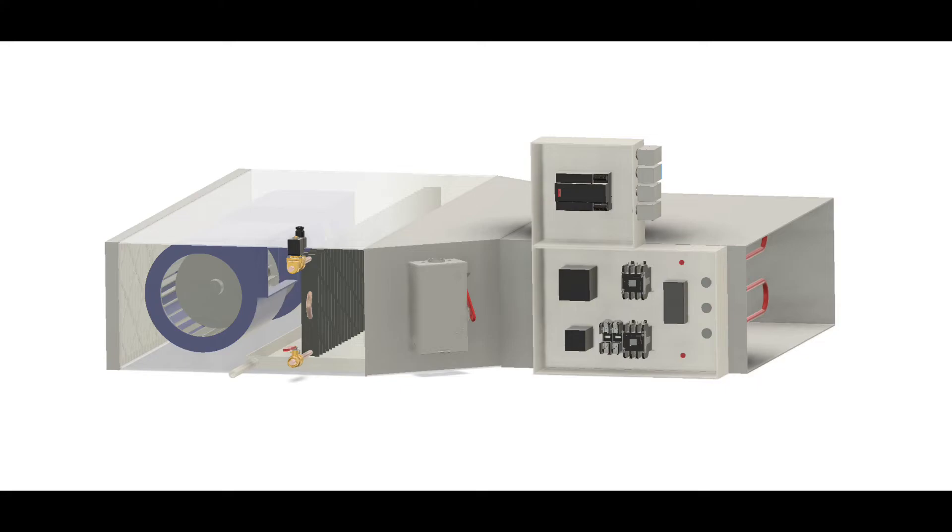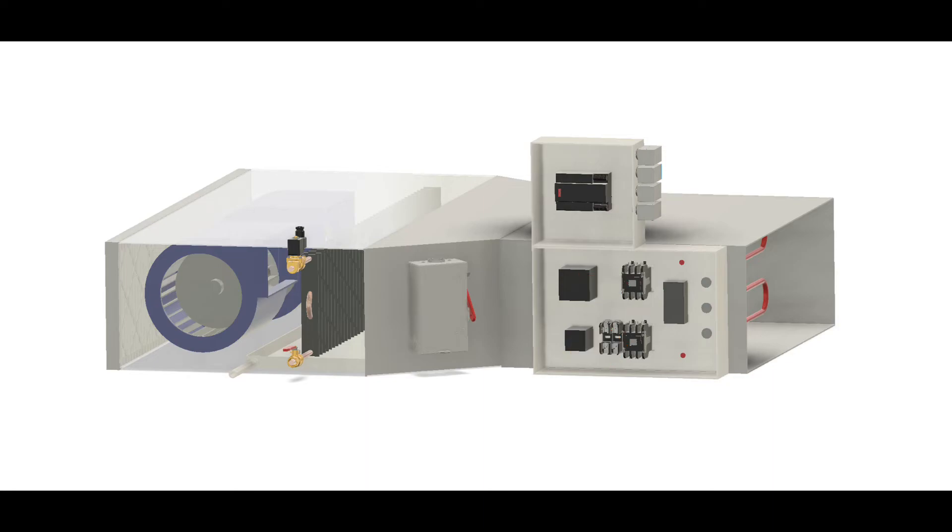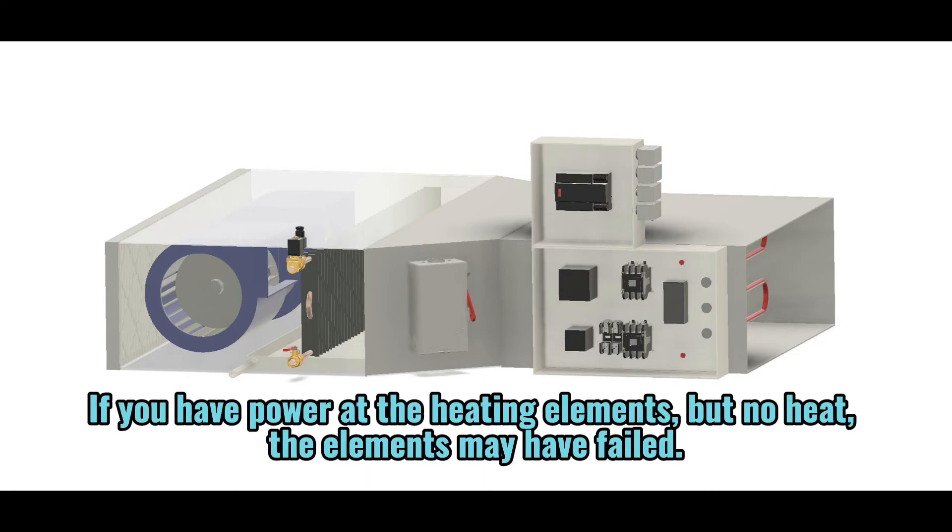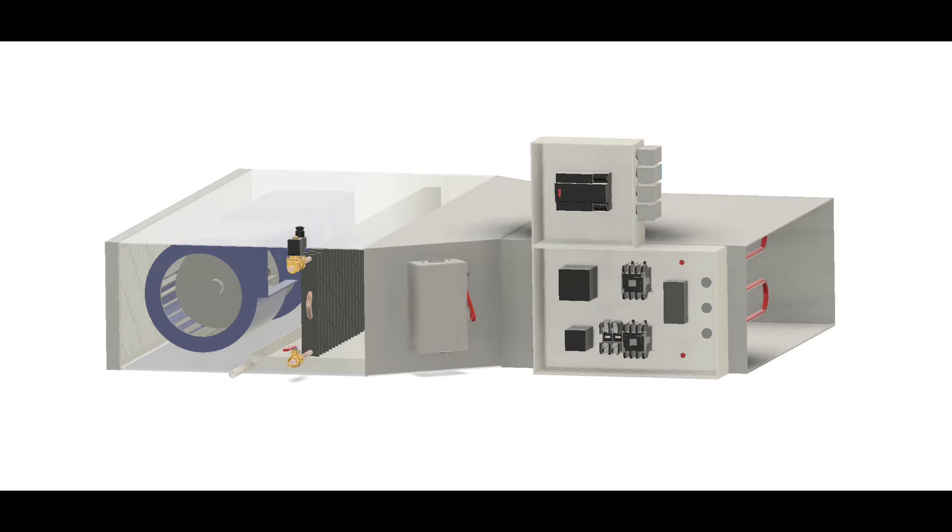Other things to check for is, are the contactors pulled in, providing that 480 volts going to the electric heating elements? If they're not pulled in, check to see why are they not. Are they getting power to the coil?